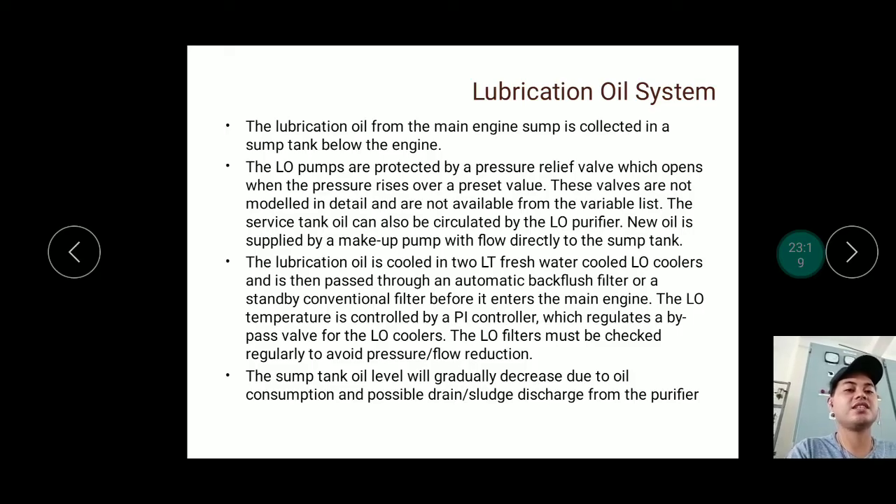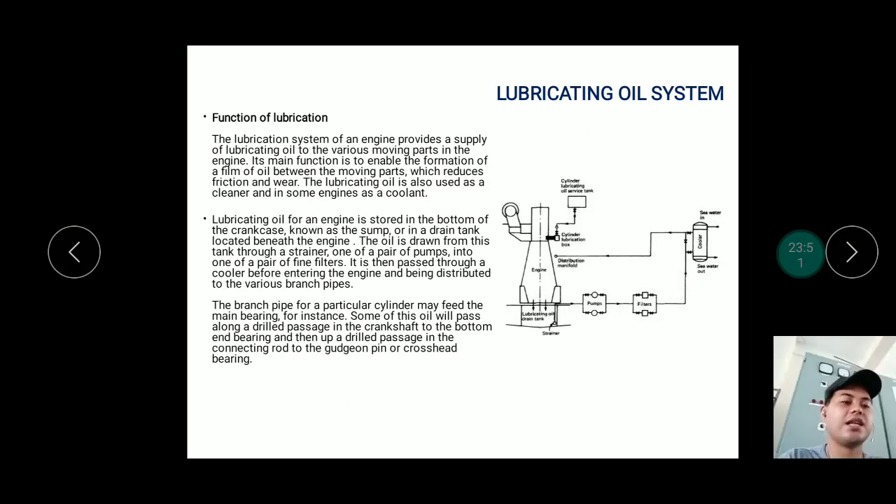The lubrication oil is cooled in two LT fresh water cooled lube oil coolers, then passed through an automatic backflush filter or standby conventional filter before entering the main engine. The LO temperature is controlled by a PI controller. Oil level may gradually decrease due to oil consumption, possible drains, or discharge from the purifier, so the tank is periodically refilled — not entirely replaced.